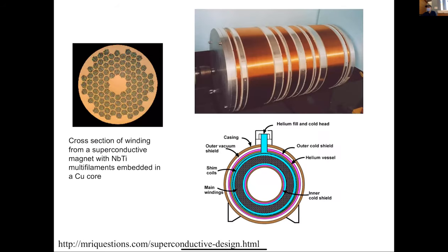This is an example of what the main coil looks like in cross section. It uses superconducting wire — niobium titanium is typically used — cooled with liquid helium. These are very nearly zero-resistance magnets: once you charge the magnet with current, the current just keeps flowing. The main thing is to make sure there's enough liquid helium to keep everything cold.